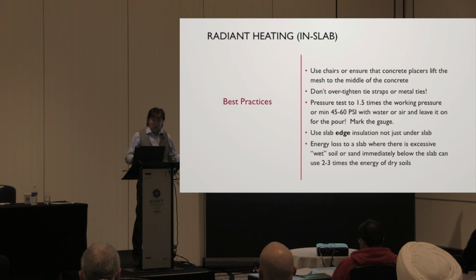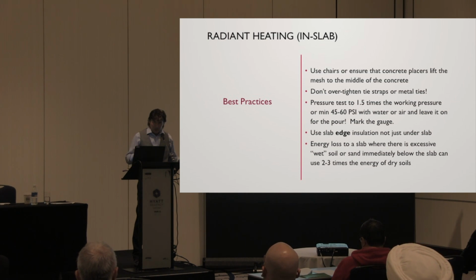But let's just say we're insulating the whole slab, which is good. If there's a lot of moisture under there, and I mean a lot of moisture, if it's soaking wet, how about you think about not putting radiant slab down there, because insulation is a function of time, really. It's going to pull all of that energy out of that slab. So it's good to understand what your water level is below a radiant slab. If there's too much water, maybe don't do it. How about that?